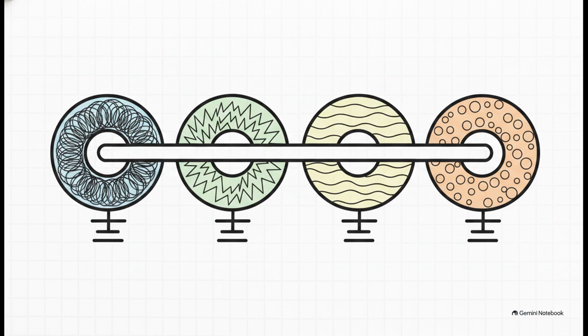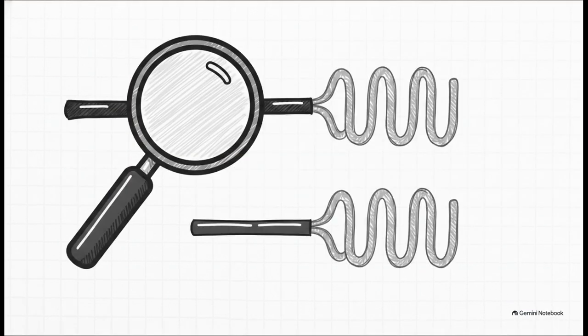They are all independently grounded, but here is the real secret sauce. They operate with completely unique behaviors. Why? Because the actual physical iron core material used for each individual secondary winding is fundamentally different. And you can spot this immediately in the field.